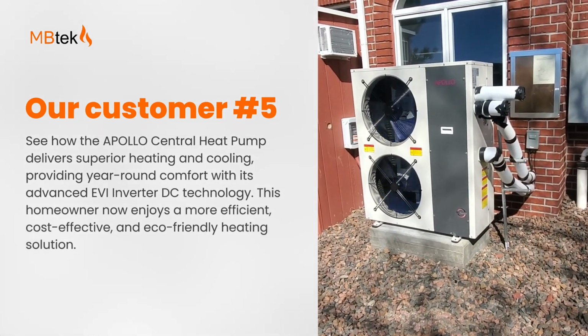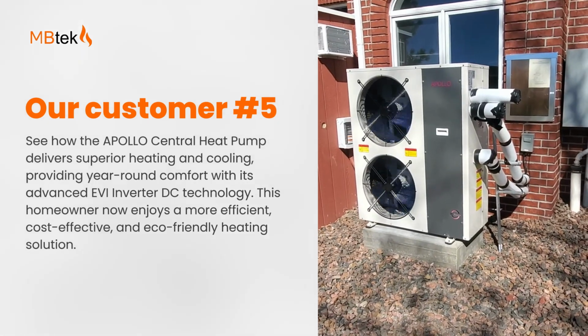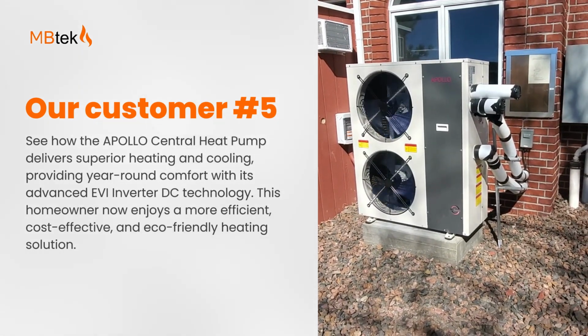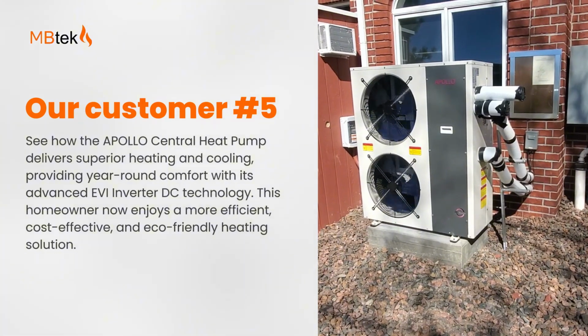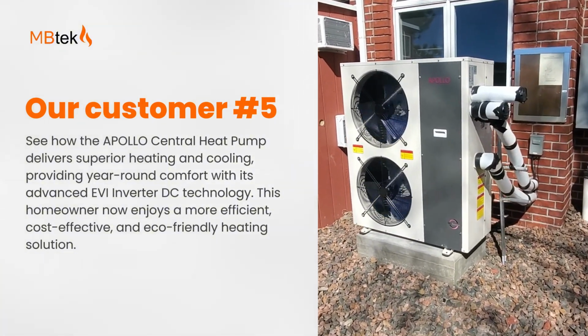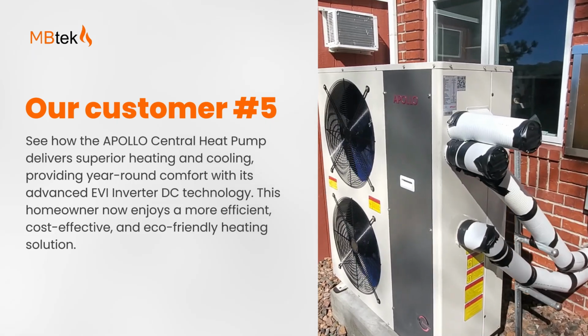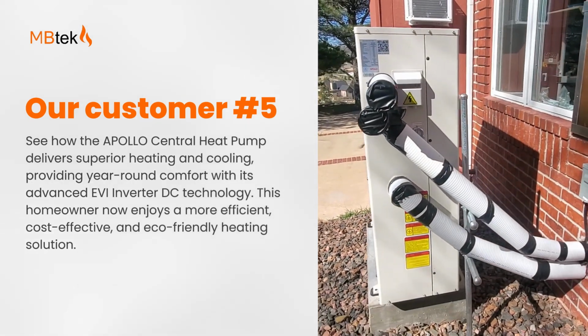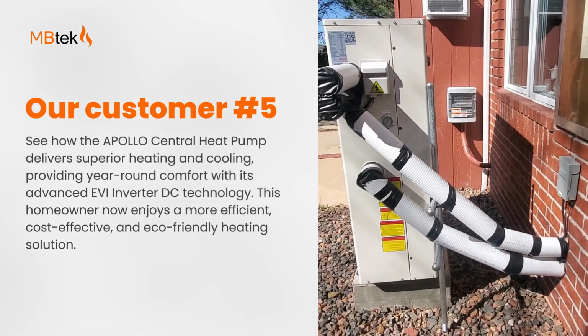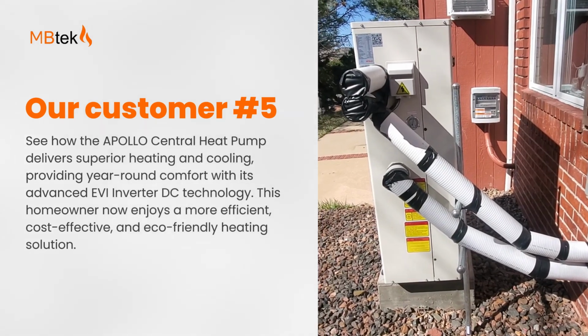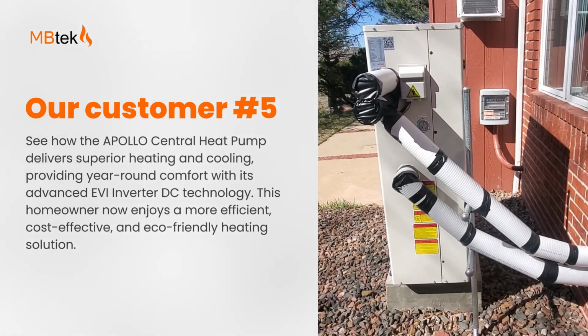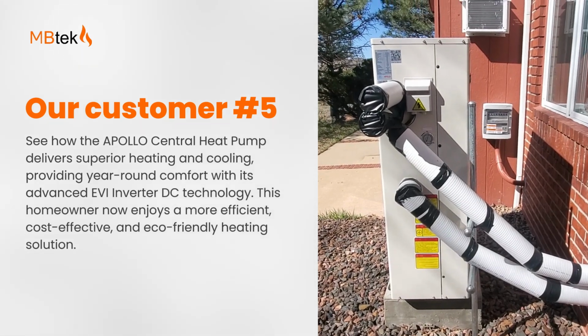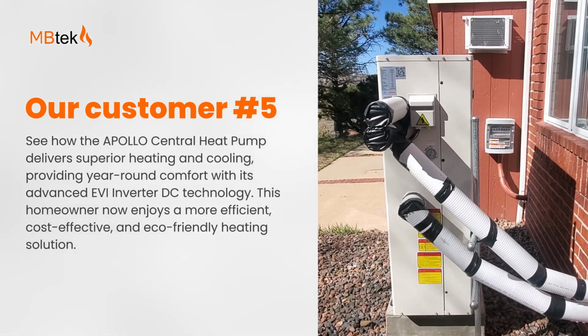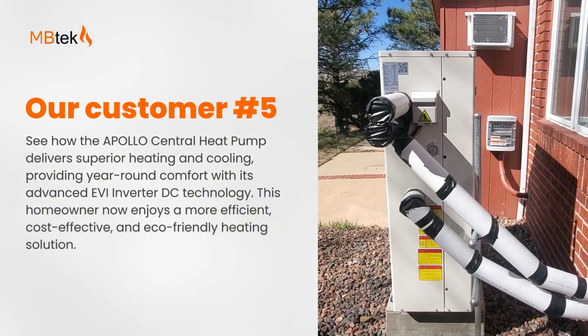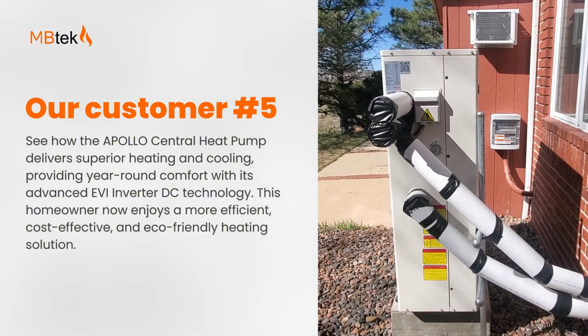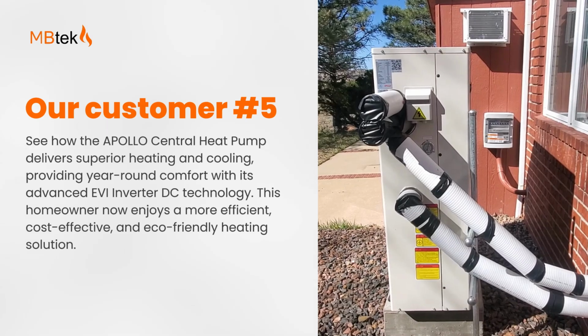You can hear the heat pump now ramping up a little bit from the low load condition startup, but it is very, very quiet. I'm going to move in closer so that we can see the side view of the unit. The 1-inch piping comes from the house through the unit and back through the house. The extra pipe that shows on the top of the pipe there is an actual covering of the vent. I got an air vent on the piping to get the air out of line.